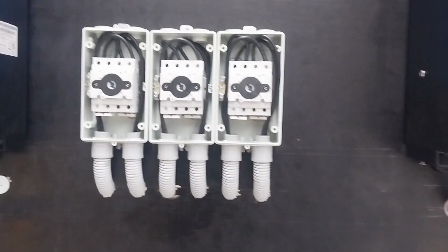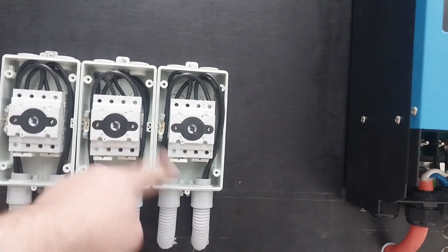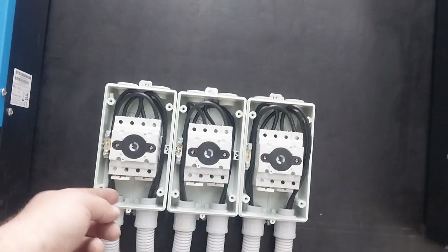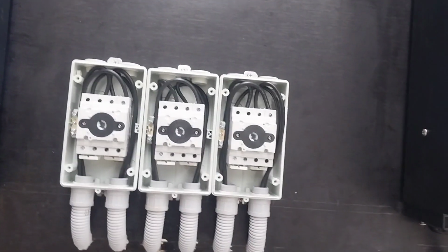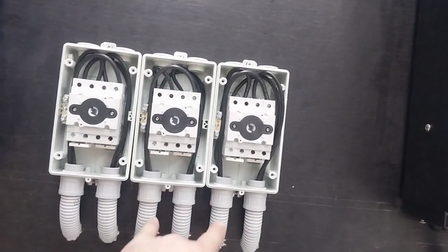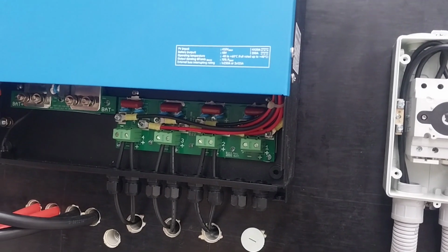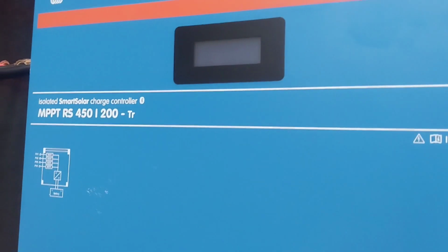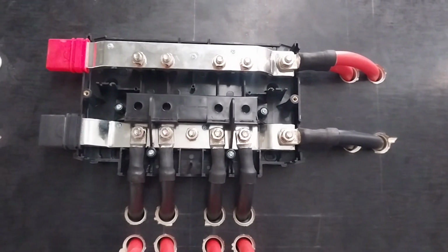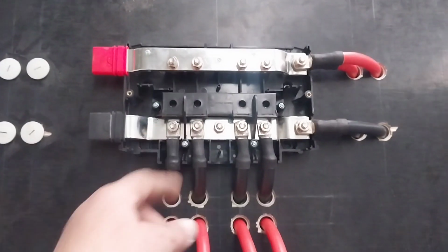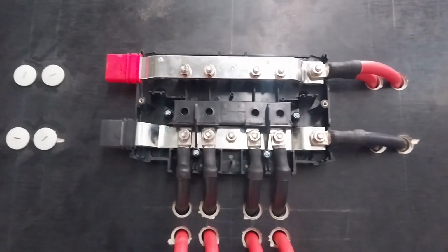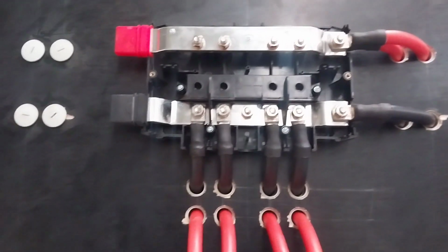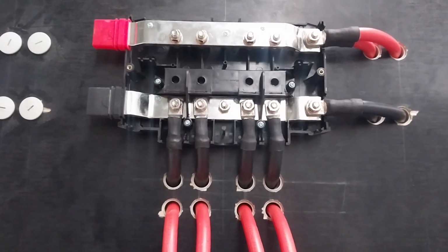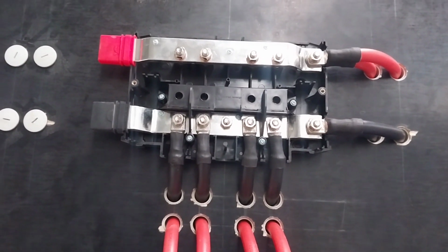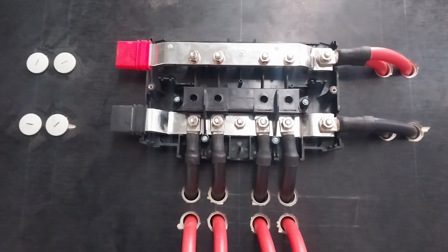Now, I've got the rooftop DC isolators here, in and out, with some links in the bottom. The right-hand side is from the roof, the left-hand side is going off to the RS450-200. So all of the slack from these ended up here, so these had to be perfect length, which is the Achilles heel of the job, as I mentioned earlier. I've got a plan for this, if I do it again. There are pluses with this method and negatives.